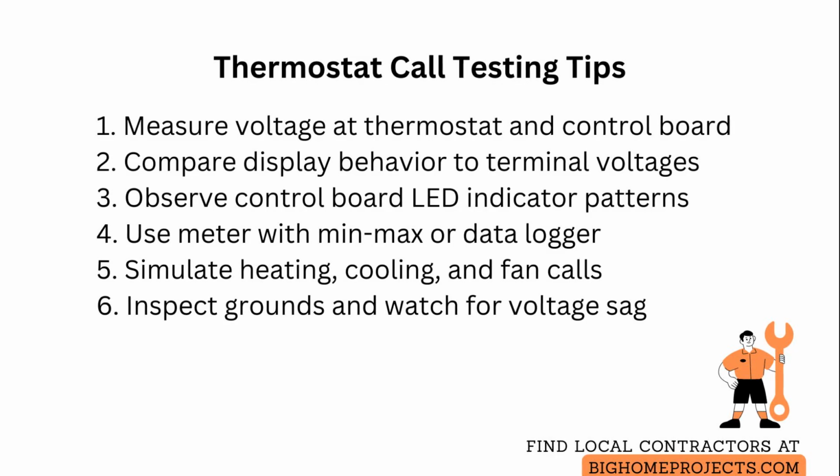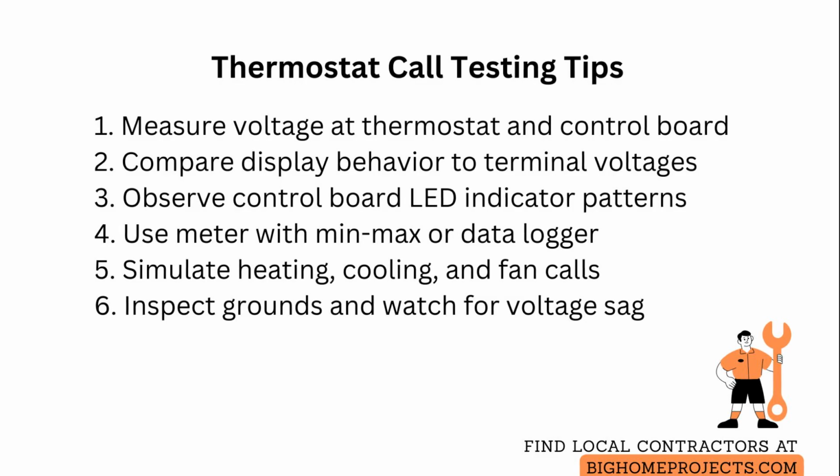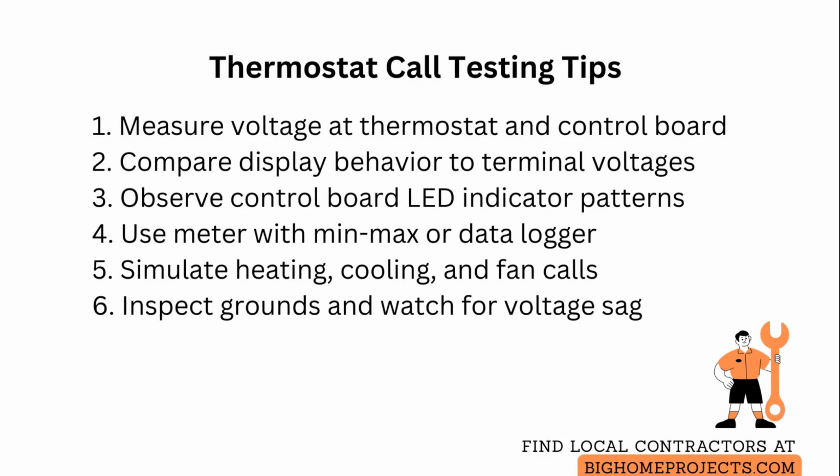Listen for relay clicks and feel for faint vibrations that indicate engagement even when the system does not start, because mechanical contacts can fail under load. Check the thermostat display for delayed changes or error codes during the call, and record timestamps of any anomalies to correlate with control board behavior.